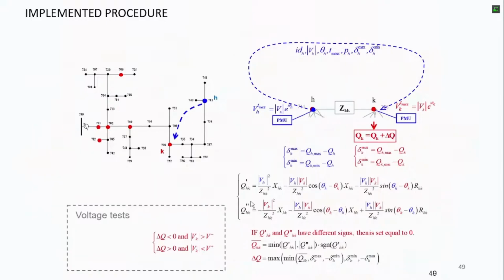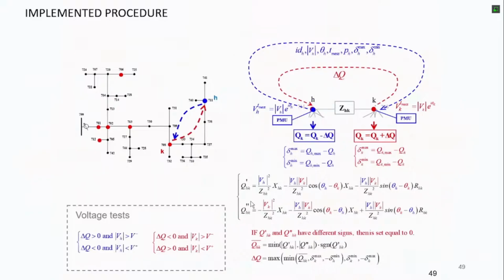And so you see that one is taking a reactive power and communicating to the other the value, and the other compensates the other way. So if one injects, the other consumes, and vice versa. This is in agreement, and this is for two. And then it is repeated.